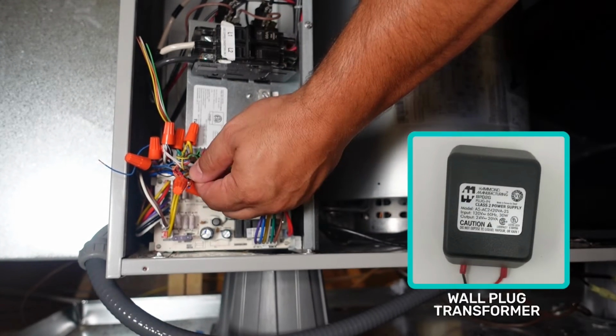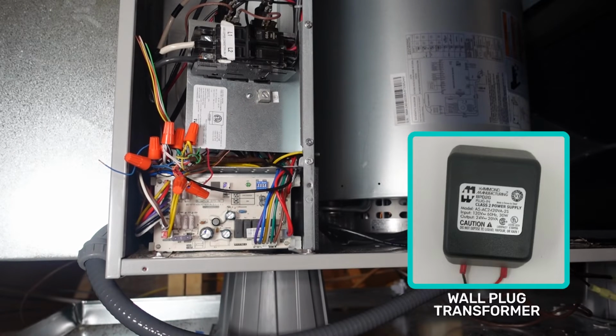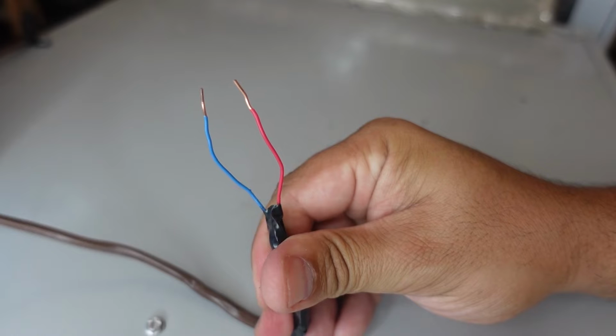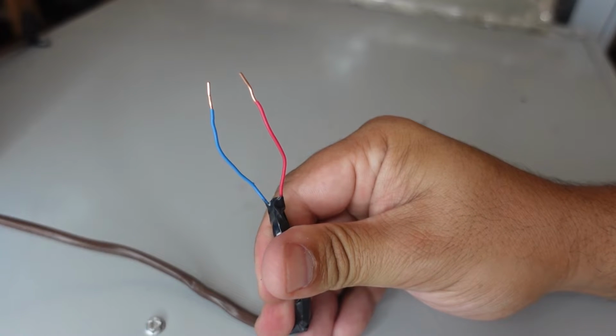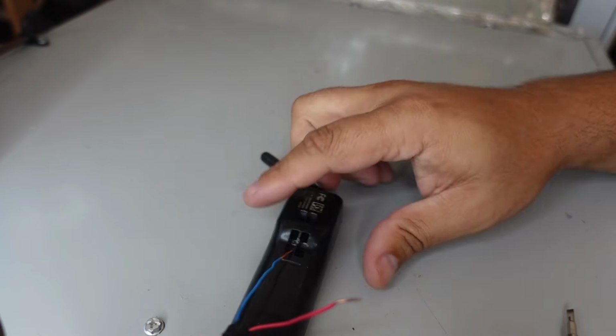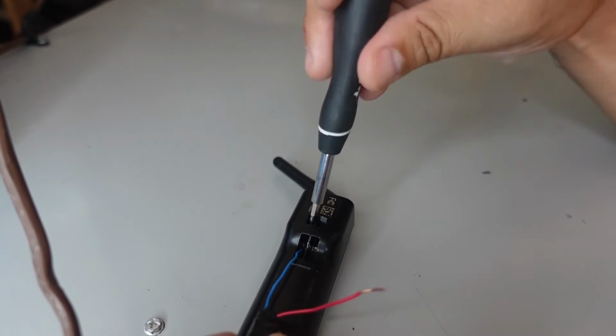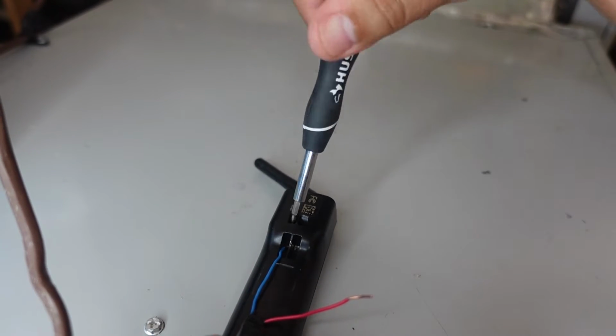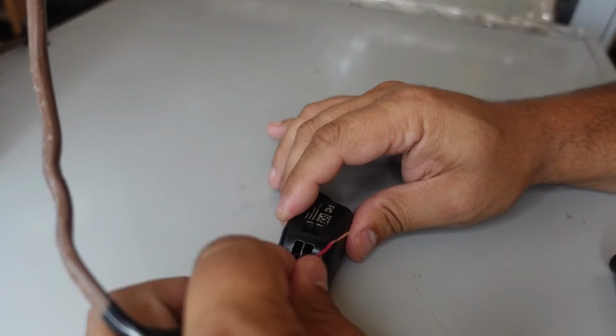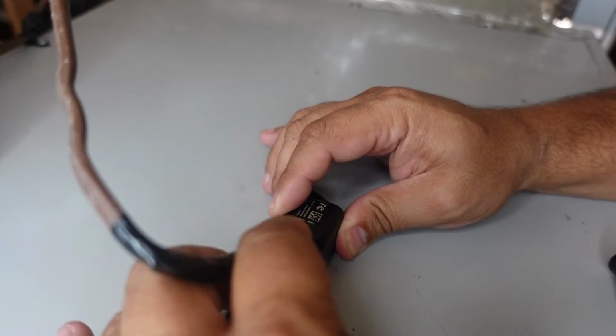You can also use a wall plug transformer if you don't want to power the monitor from the air handler. After connecting the power source, strip back 2 inches of jacket and half an inch of insulation on the monitor side of the wire. You don't have to worry about which wire goes into which connector. The cables are reversible for both AC and DC power.